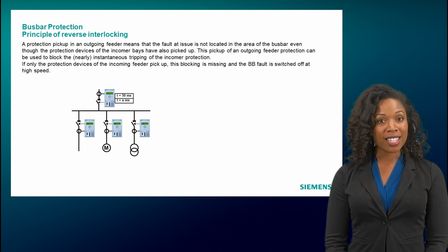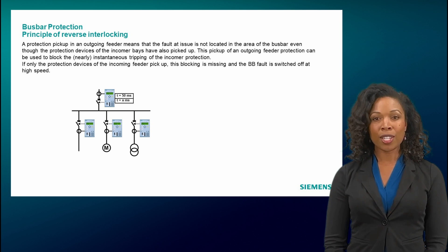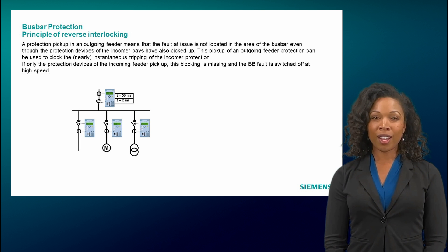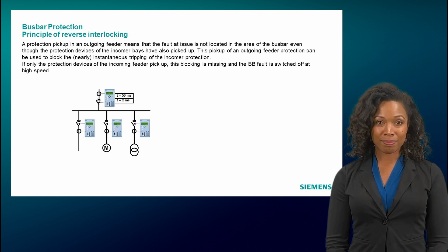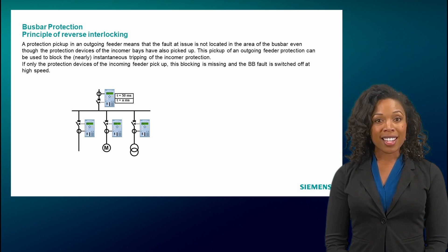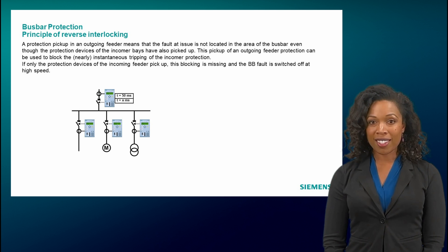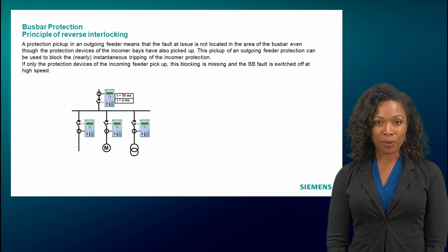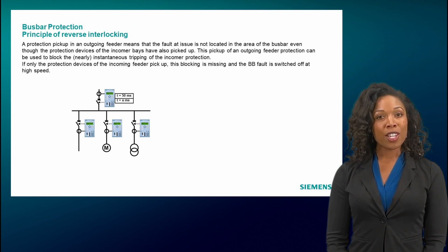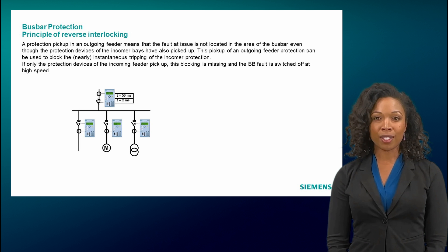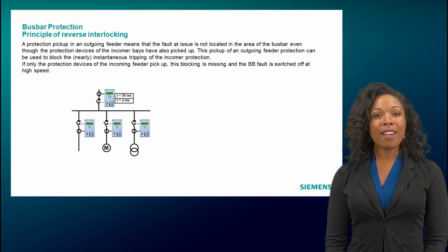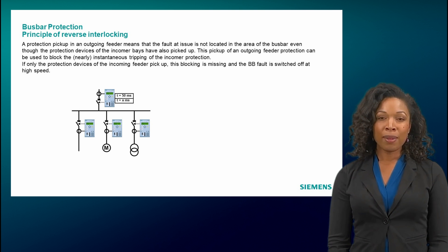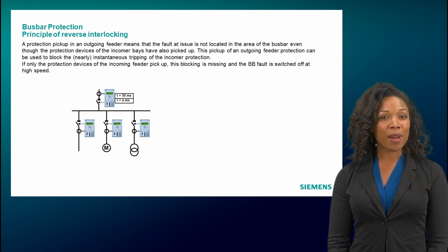The principle of a reverse interlocking system can be explained very well by the switchgear shown. First of all, we assume that the incomer feeder shown above is the only feed-in, and all outgoing feeders below are consumers. In this constellation, the protection device in the incomer feeder has two tasks. First, the device forms the backup protection for the protection devices in the outgoing feeder — for example, a fault in the feeder is recognized by the feeder protection, but the tripping must be set to a delay so that the feeder protection has the chance to clear the fault selectively. Second, the device represents the busbar protection and must trip as quickly as possible in the event of a busbar fault.